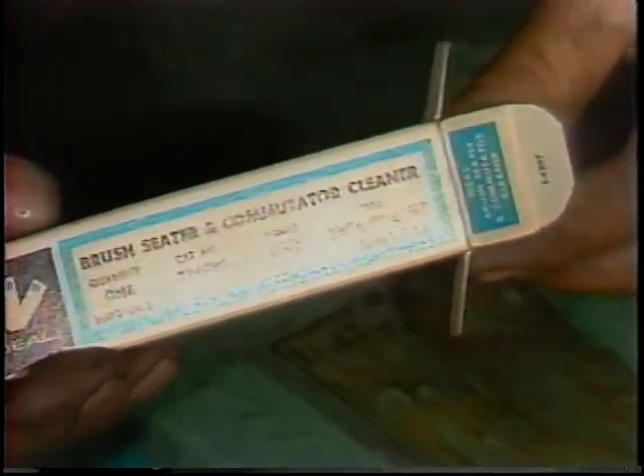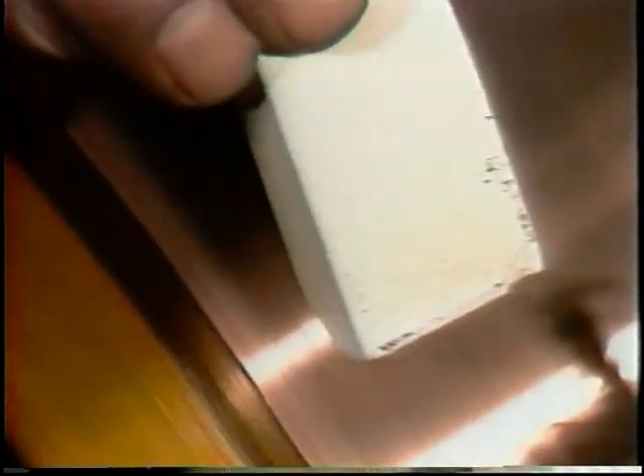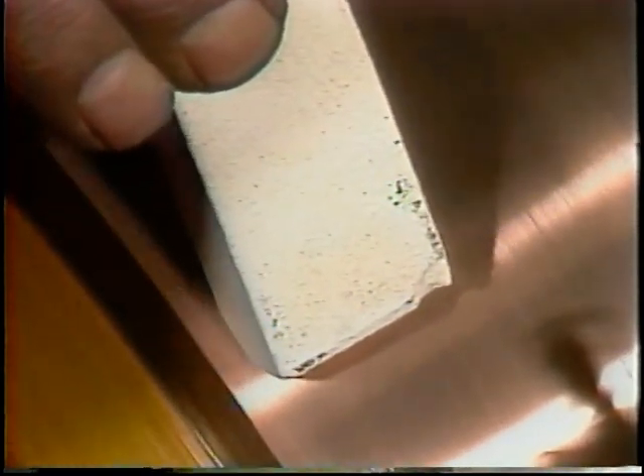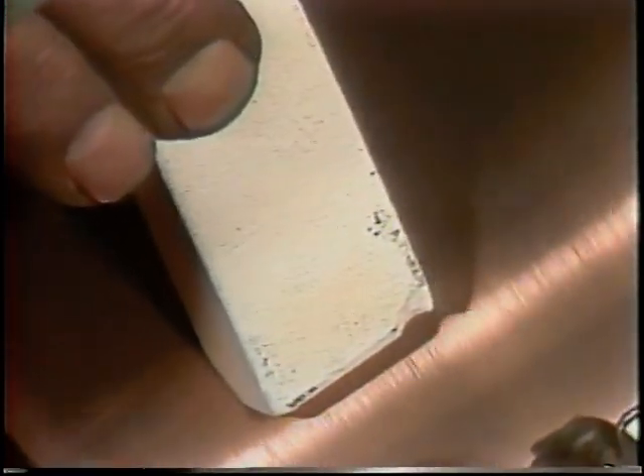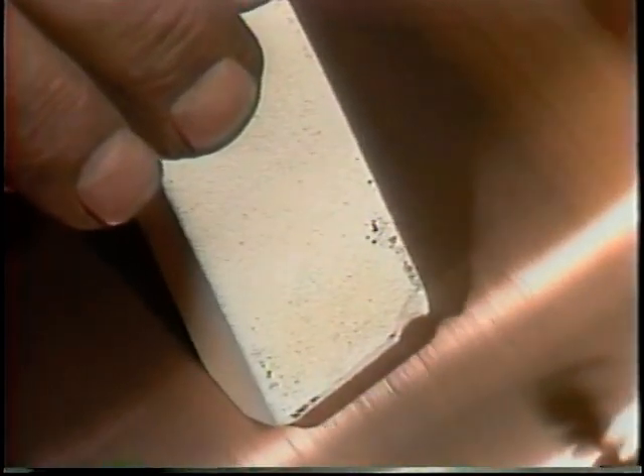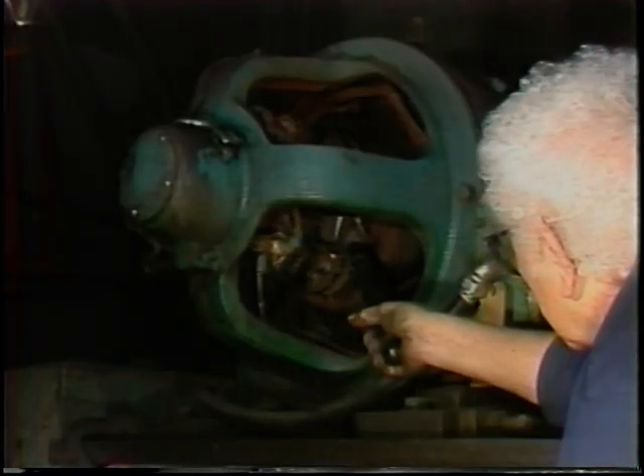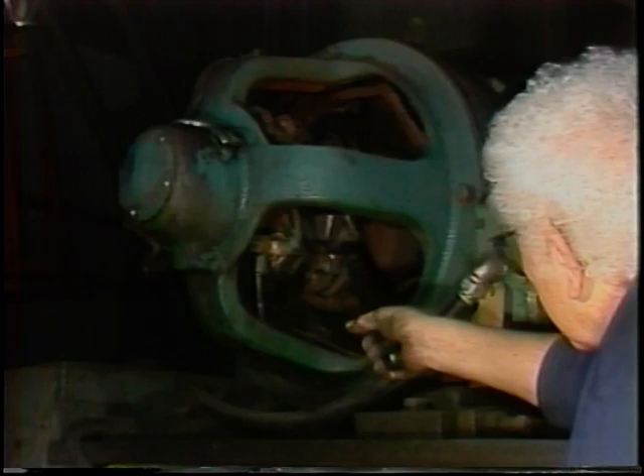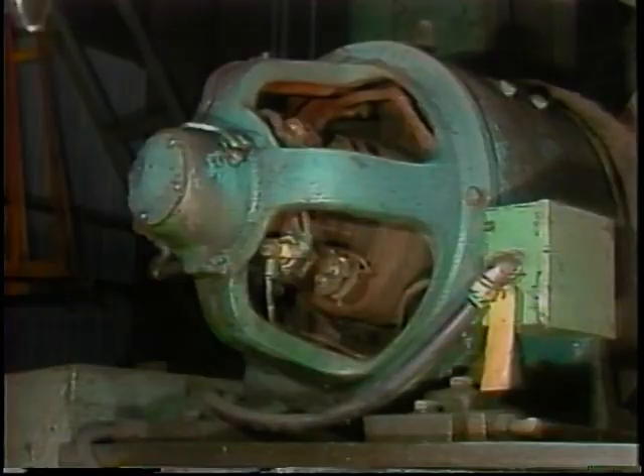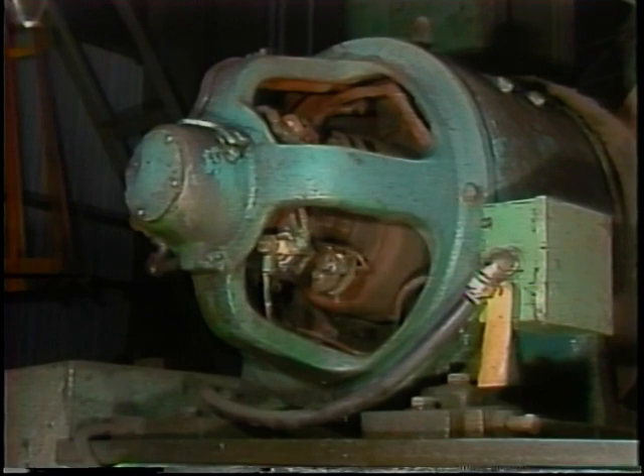A brush seating stone is also available. It is held against the commutator as the motor runs and will both polish the commutator and wear off the end of the brush slightly for a better fit on the commutator. Stones for resurfacing the commutator are also available. They must be used carefully, and you've got to know what you're doing. DC motors are expensive and easily damaged. Finally, after you've installed new brushes, check them for sparking when the motor is running to make sure you've installed them correctly.